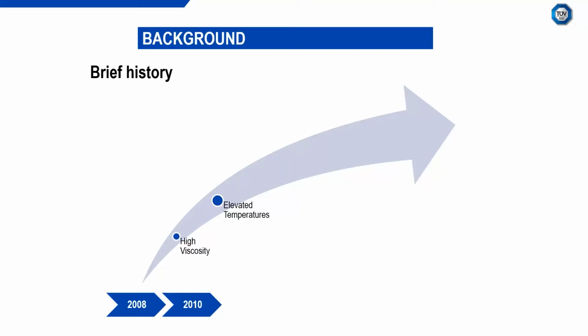It was always thought that temperature didn't have a big effect on flow meters, and that's historically due to the flow meters being positive displacement, turbine, differential pressure devices. But this end user wanted to know if there was an effect of elevated temperature on Coriolis flow meters. So we managed to get a couple of Coriolis flow meters from the main manufacturers, a variety of sizes, and completed some preliminary investigations at NEL using our oil flow facility.